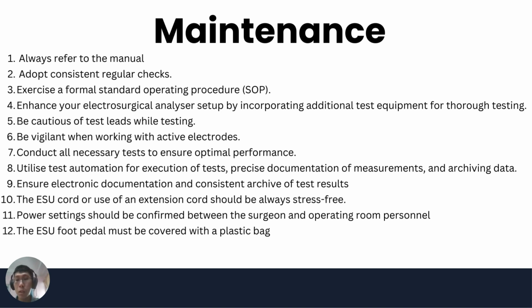Tenth, the ESU cord should always be stress-free. The cord should lie flat and be free of kinks or knots. Eleventh, power settings should be confirmed between the surgeon and operating personnel. The settings should be adjusted based on factors such as patient size, type of active electrode being used, the proximity of the patient's return electrode to the operative site, and recommendations provided by the manufacturer. It is always advisable to start with the power setting at the lowest level necessary to achieve the desired tissue effect. Twelfth, the ESU foot pedal must always be covered with a plastic bag to prevent contamination during the surgery.